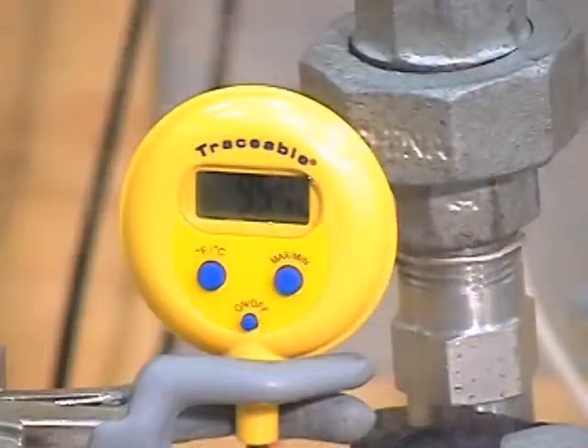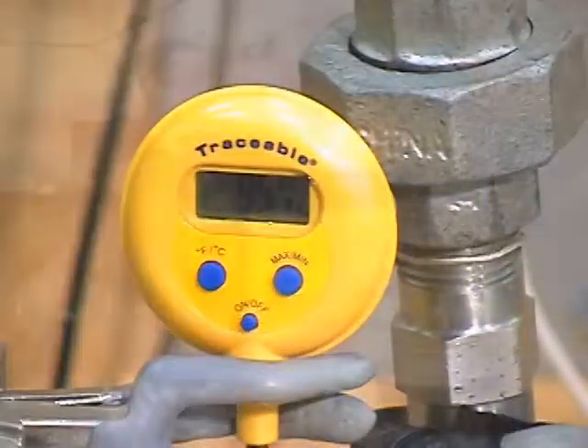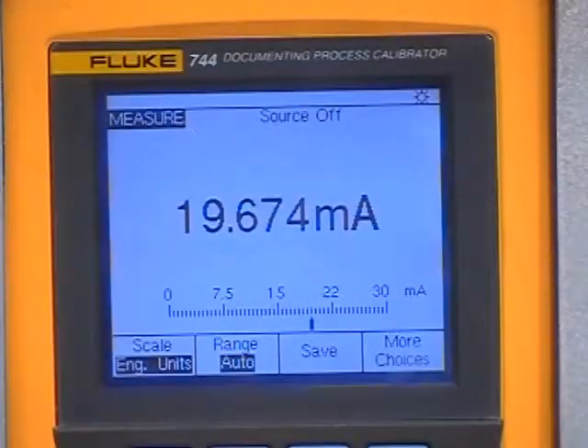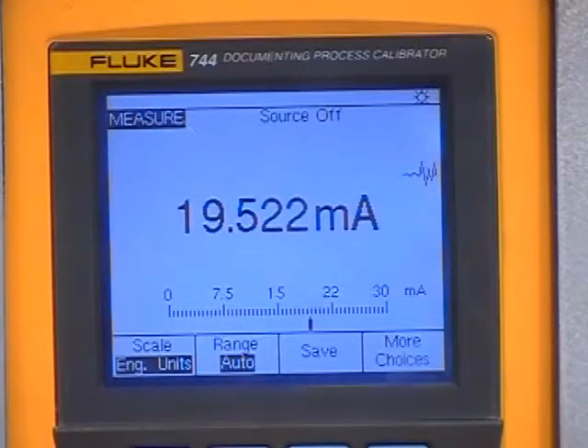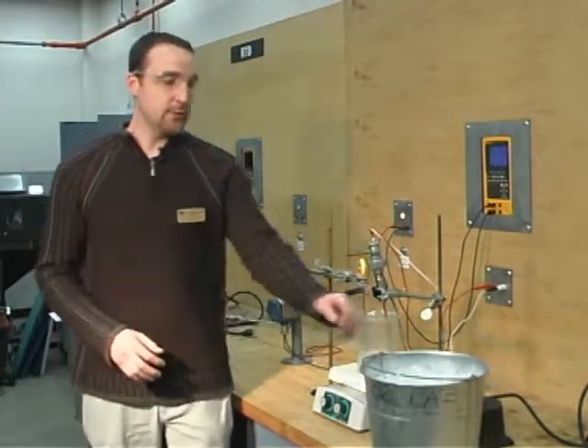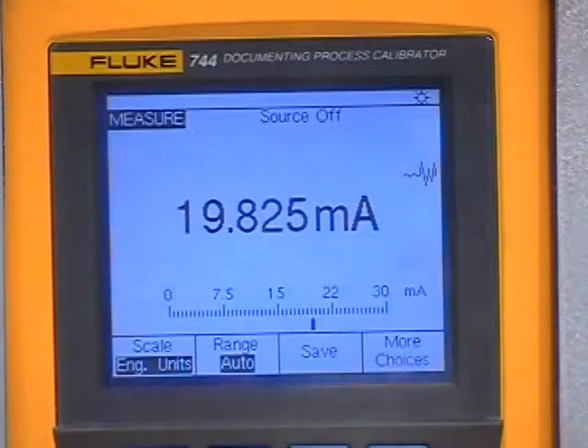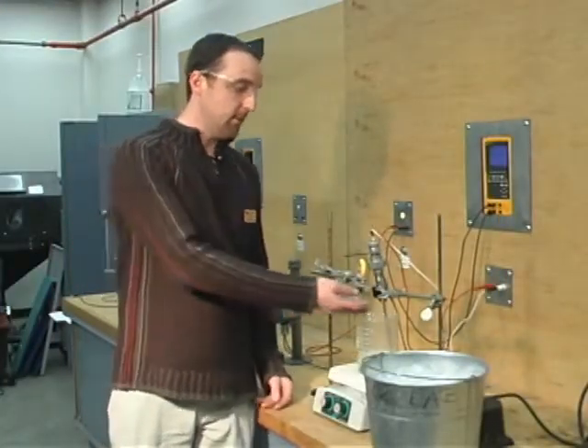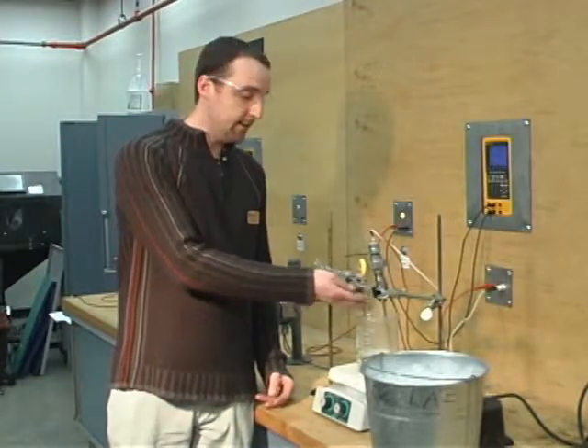Currently we are reading 99.8 degrees Celsius, and our transmitter is reading 19.635, but it is slightly changing so I will wait. Currently we are at 99.8 degrees Celsius, and we are reading 19.84 milliamps. Now we are going to decrease our temperature by 10 degrees using ice. We will slowly turn off our heat and introduce the ice. Our next point will be 90 degrees Celsius.